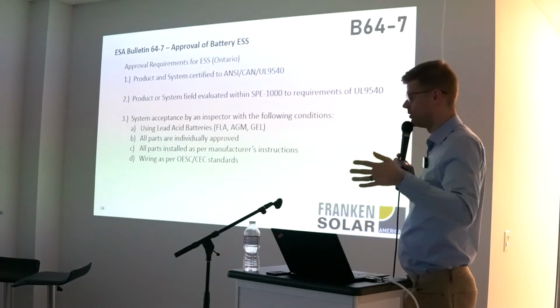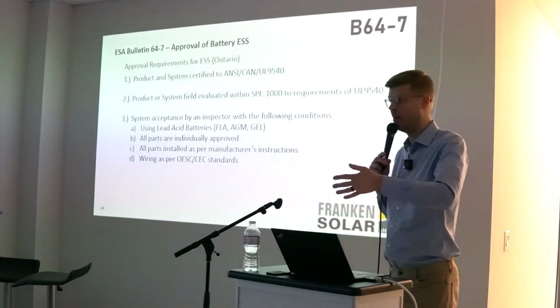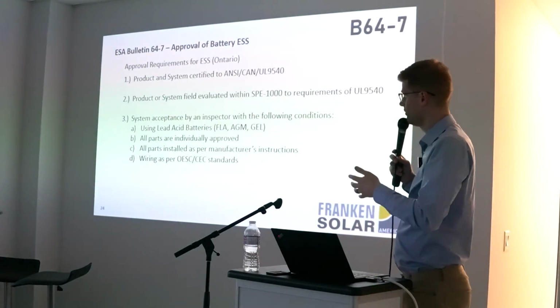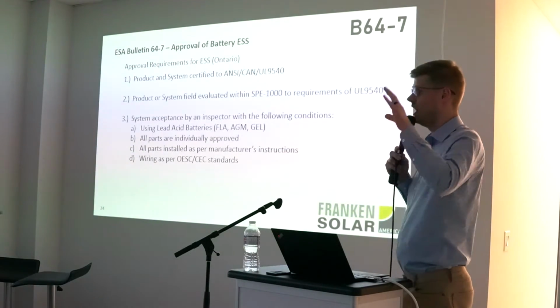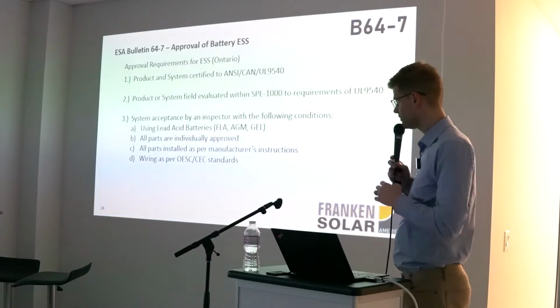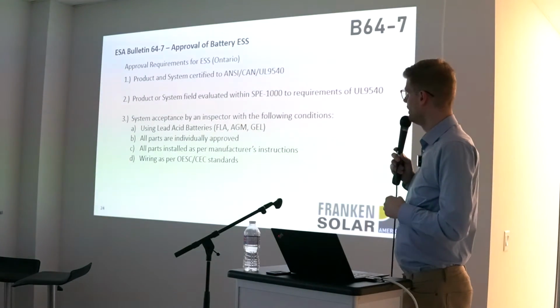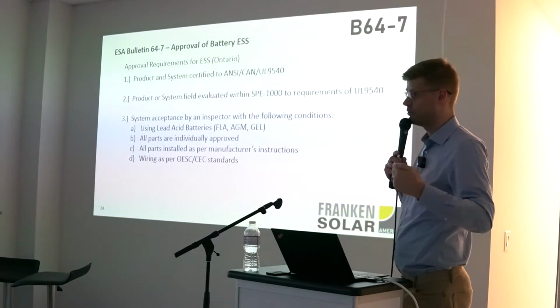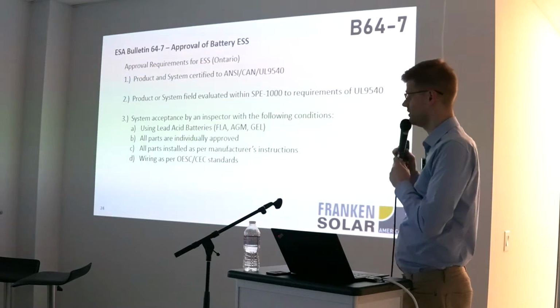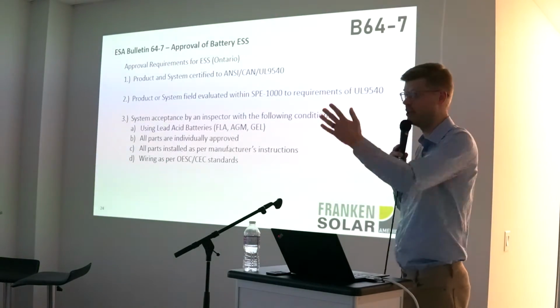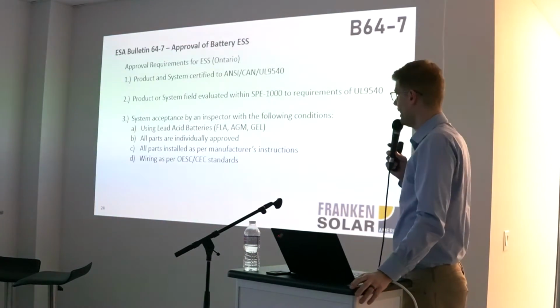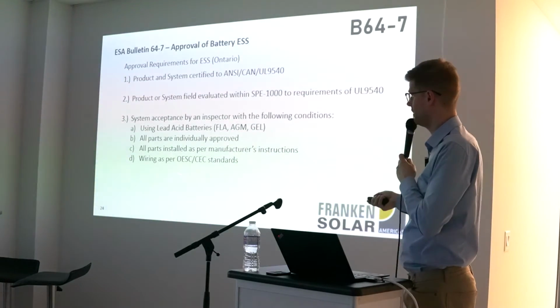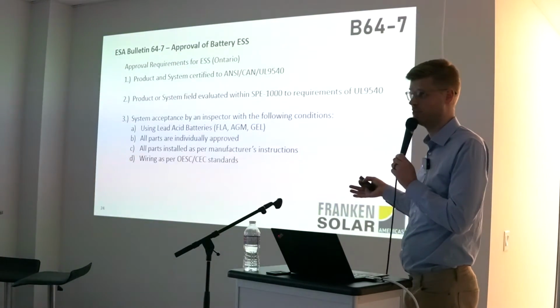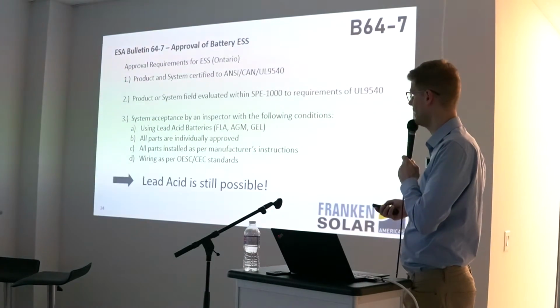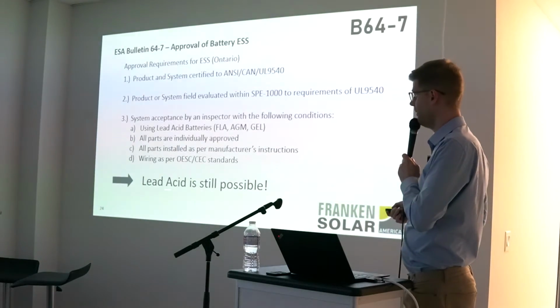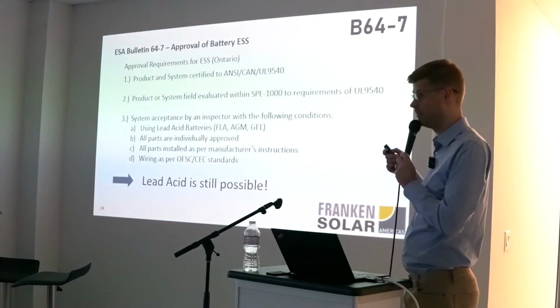All the components you're using, so the inverter, the transfer switch, your DC combiner if you have one, a charge controller if there's one involved, any other component being used, need to be approved to their respective certifications or approvals. And all the parts need to be installed according to the specific manufacturer's specifications. The inverter has a manual that states it has to be installed a certain way. Your electrical panel needs to be installed in a certain way. On top of that, you have to use the Ontario Electrical Safety Code wiring standards, which is pretty much the standard electrical installation any electrician is following anyway. And if you fulfill all of those conditions, then you can still use lead-acid batteries in residential dwellings.